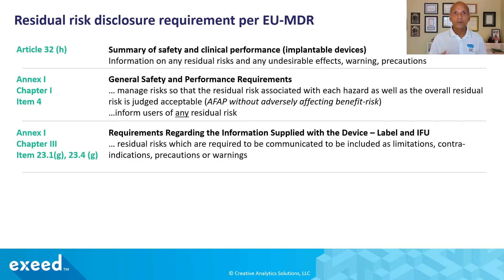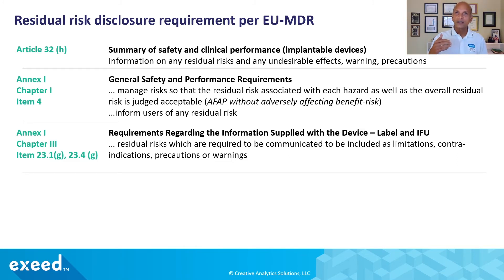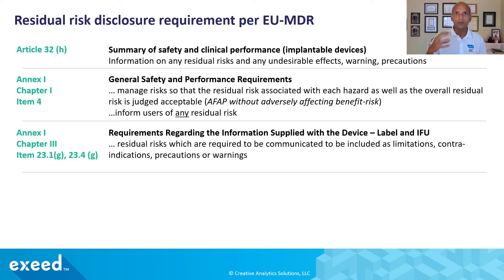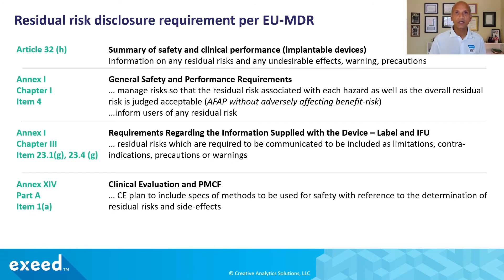In Annex 1, Chapter 3, additional requirements related to information supplied with the devices — the label and the IFU — residual risks which are required to be communicated should be included as limitations, contraindications, precautions, or warnings. Depending upon the severity of the consequence of those residual risks, you can organize the communication accordingly so that it can be more organized, more informative, and more actionable.